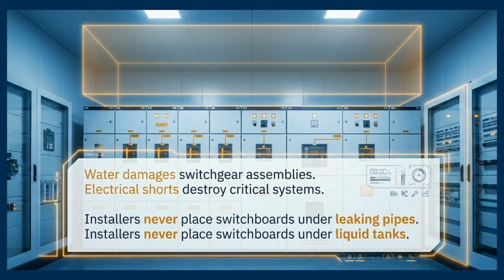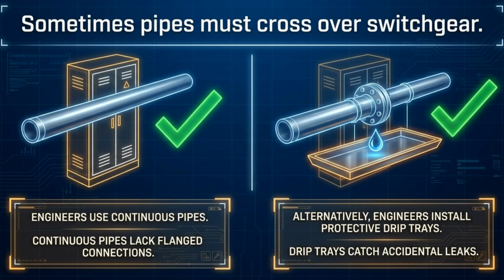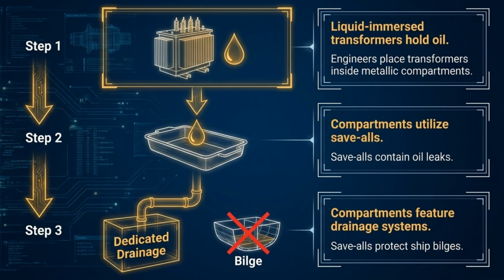Switchboard protection is equally critical. To prevent water damage and electrical shorts, installers are strictly prohibited from placing switchboards under leaking pipes or liquid tanks. If pipes must cross over switchgear, engineers use continuous, flangeless pipes. Alternatively, protective drip trays are installed to catch any potential accidental leaks. For liquid-immersed transformers, safety is managed in 3 steps: placing units in metallic compartments, utilizing save-alls to contain leaks, and ensuring dedicated drainage to prevent oil from reaching the ship's bilges.